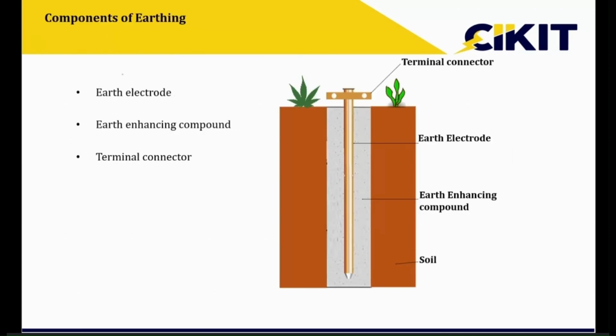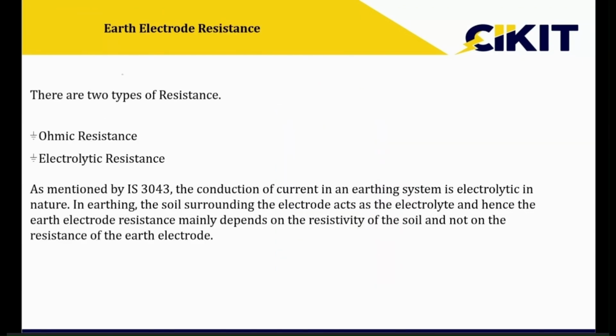If you take earthing, there are three main components. One is the earth electrode, the second is the earth enhancing compound, and the third is the terminal connectors. The terminal connectors are also very important. Even if the conductors are good, and even if I'm using a highly conductive material, if the terminal connection is not proper, there is no purpose in it. The current won't get discharged properly. So the terminal connection is as important as the earth electrode which we are using.